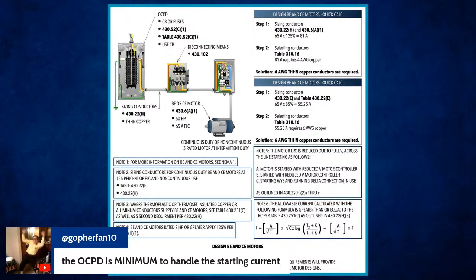Now, you can go below that if you want, if it'll allow the motor to start, but this is a minimum starting point for you. If you look at that table for a squirrel cage motor, it's going to tell you to take that at what? 250%. So I'm going to take the 65 amps times 250%. That's going to give me 162.5 amps. It says I can't exceed the calculated value, so I go back to Table 240.6(A). The next size below that is 150 amp.